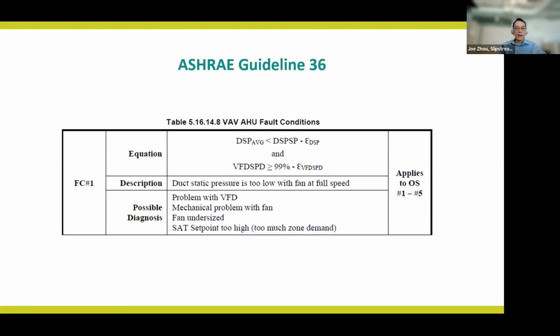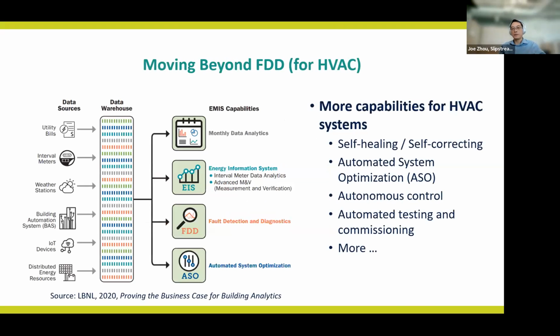So it gives the possible diagnostics, but it cannot pinpoint which specific fault results in this phenomenon of the duct pressure being too low with the fan at full speed. This is a more basic rule-based diagnostic embedded in ASHRAE Guideline 36. There are 14 other similar equations, and it gives you a table with what you see from the equation, a description, and possible diagnostics, but it cannot pinpoint the specifics. That's a limitation of what you can do within the field controller.